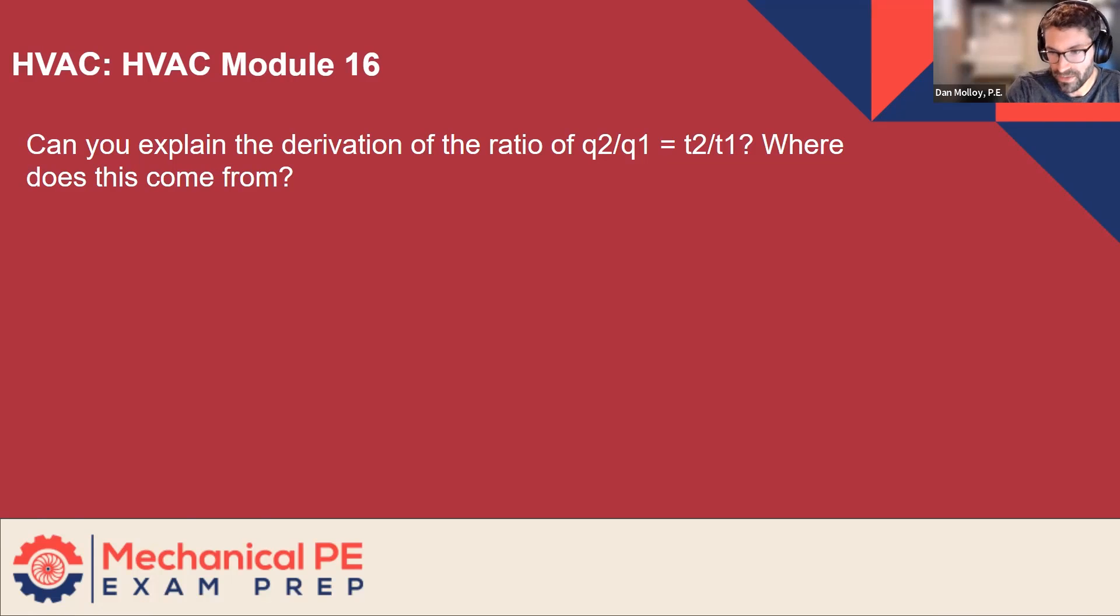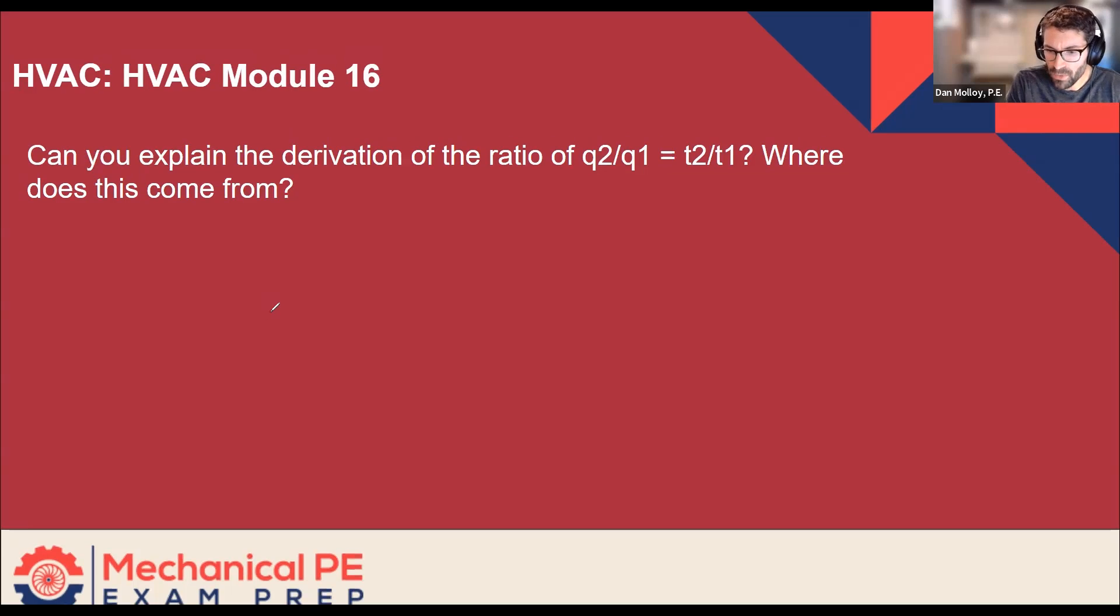So just for context, for kind of a reminder, this problem was about a fan that was used at standard temperature and pressure, and then is being utilized at a higher temperature. So the problem starts by asking you to figure out the air horsepower based on the efficiency and the brake horsepower, both of which are given. So through that, we get the air horsepower.